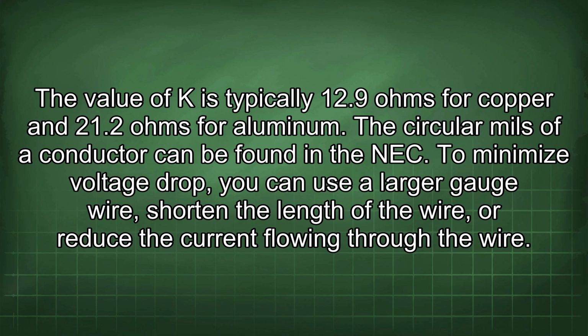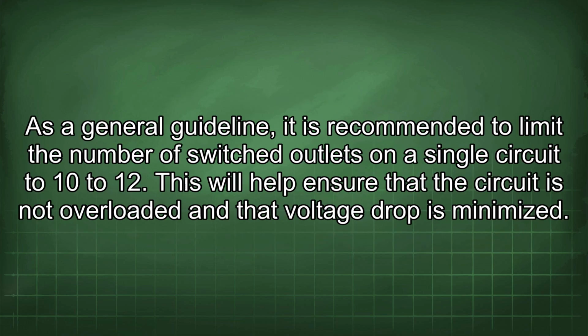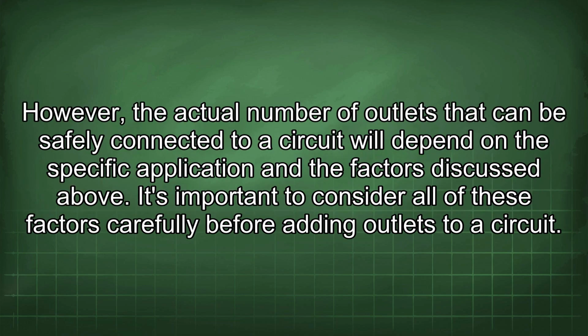To minimize voltage drop, you can use a larger gauge wire, shorten the length of the wire, or reduce the current flowing through the wire. As a general guideline, it is recommended to limit the number of switched outlets on a single circuit to 10 to 12. This will help ensure that the circuit is not overloaded and that voltage drop is minimized. However, the actual number of outlets that can be safely connected to a circuit will depend on the specific application and the factors discussed above.